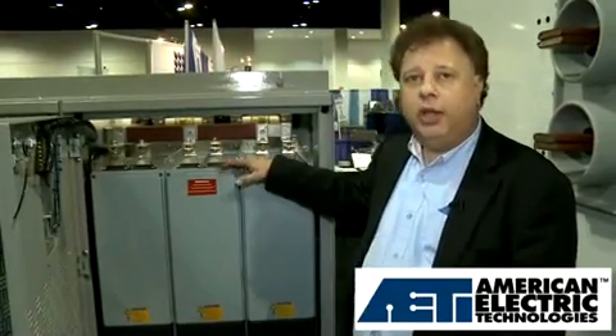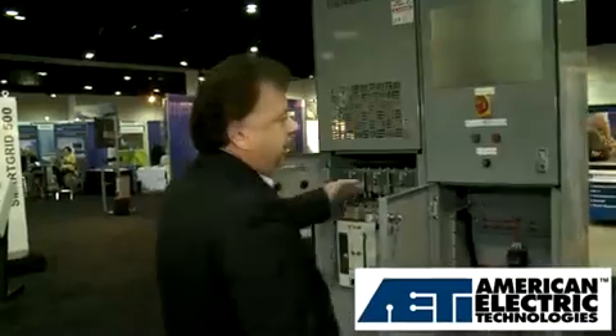It sits on the base of the turbine because what's up in the middle of the turbine at the top is the actual generator itself. All the other parts of the EWT turbine are on the ground for service and maintainability. After we go out from the output to the grid, we go through the control system, which I'll show you down here. In this section, this is where we have our breaker system and disconnect system and our PLC controls, which control the turbine. What's missing from this overall lineup is the filter section, which is about this big and this high, and it's arranged in a circle around the base of the turbine.